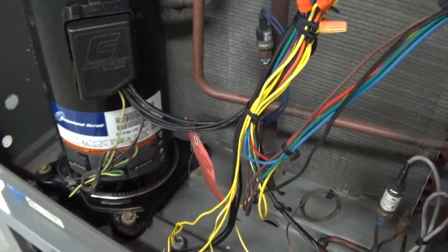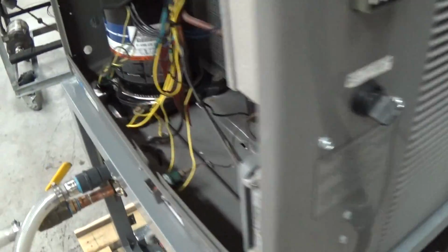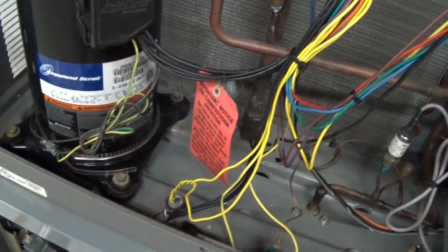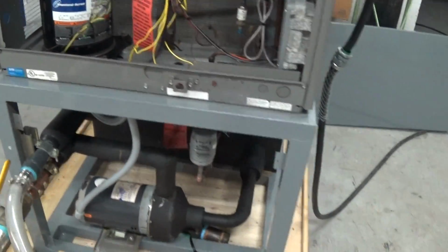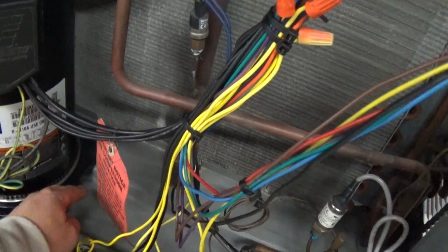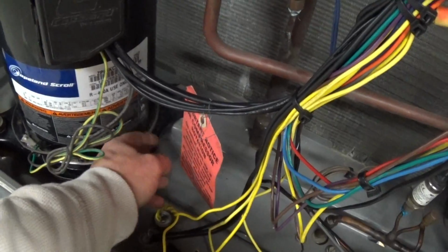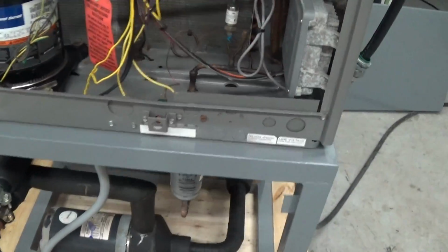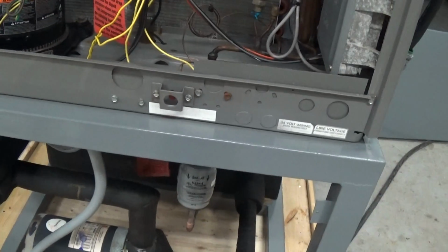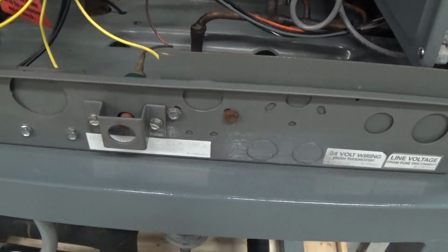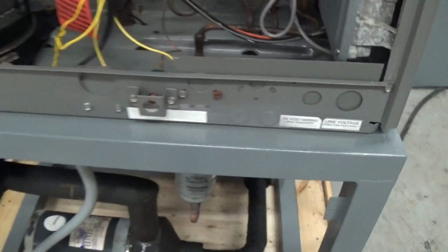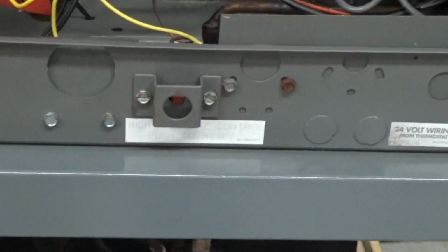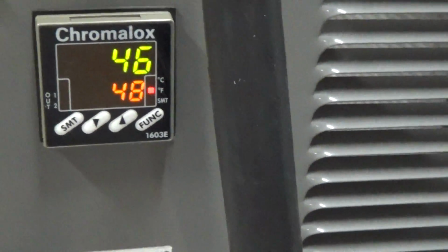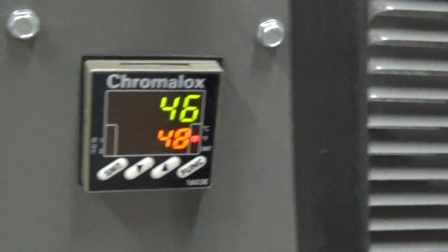As long as there's power coming into the unit, even if this is off, this crankcase heater is on, and we always want that on. It uses very, very little energy, and it's hot to the touch, but not crazy. If it ever goes into high pressure alarm, which could be due to dirty condenser coils, that's the high pressure reset switch right there. So the unit just turned off. It went, like I said, a degree or two below set point. That's about it that we want to talk about here.